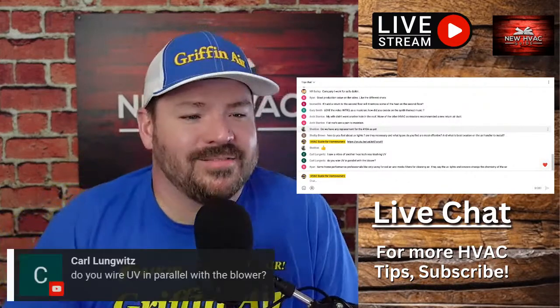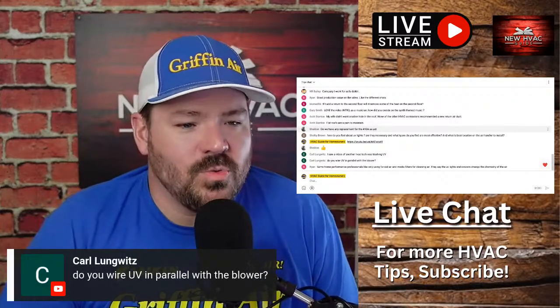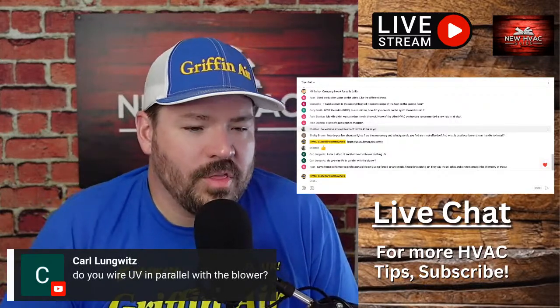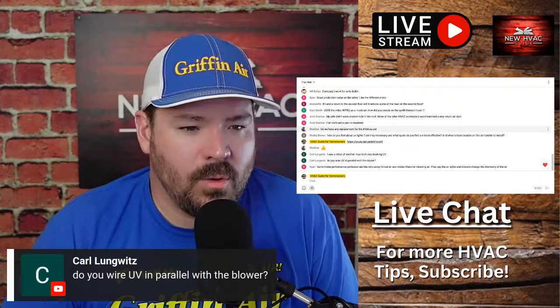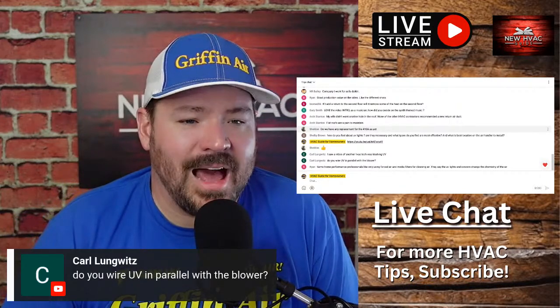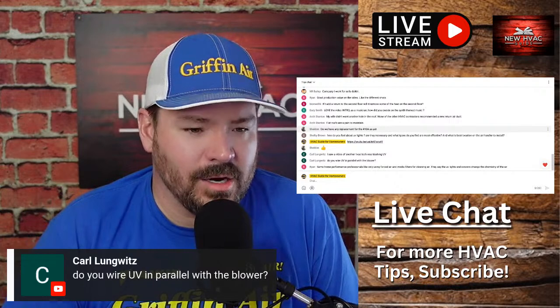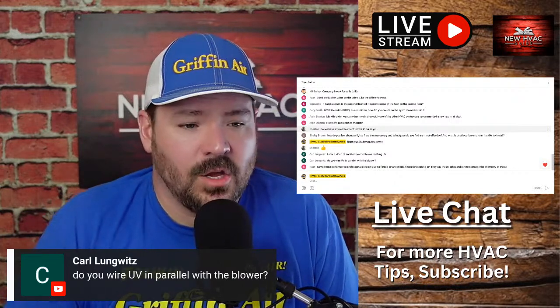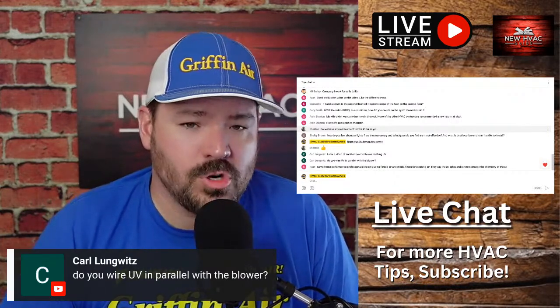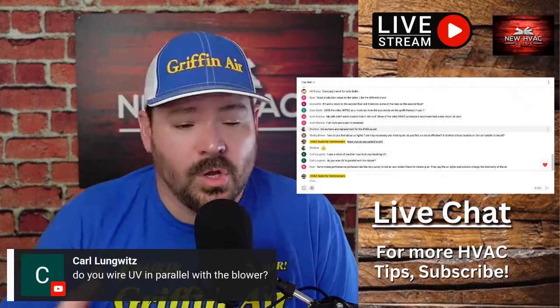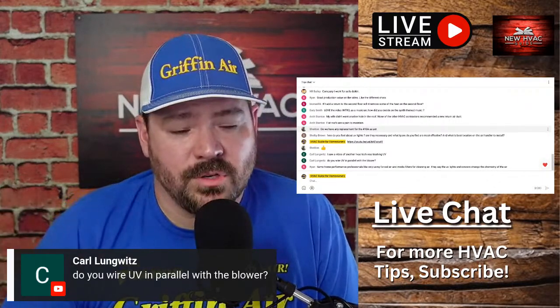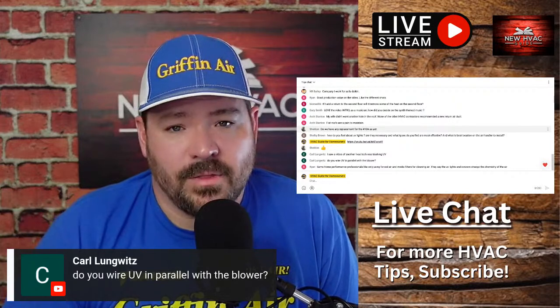Carl asks, do you wire UV lights in parallel with the blower? No, I wire them on the line voltage coming into the air handler. Most of our UV lights are 240 volt. They come with their own transformer to step it down to whatever voltage it needs, and that's how they're wired. So I don't wire it parallel with the blower.